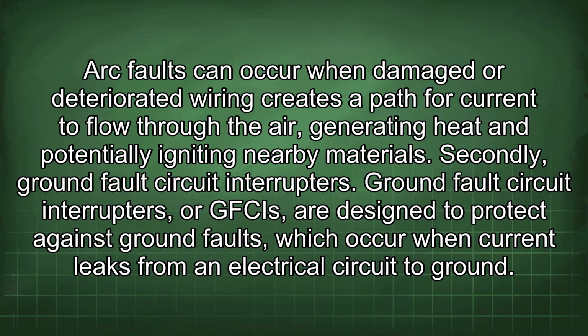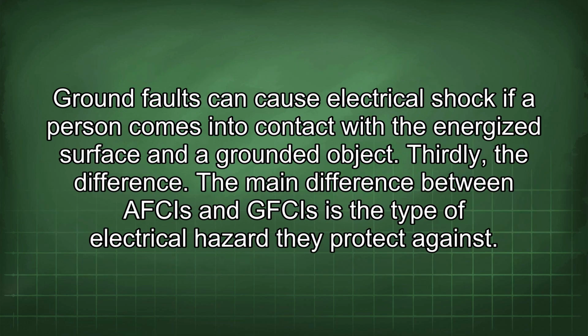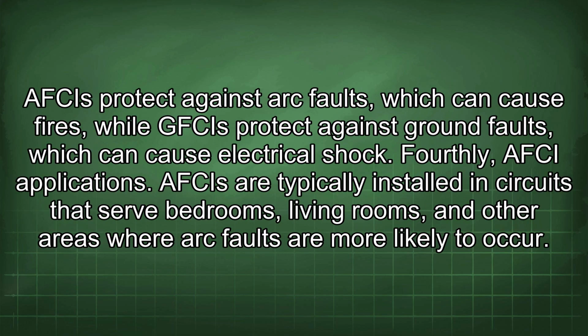Secondly, ground fault circuit interrupters. Ground fault circuit interrupters, or GFCIs, are designed to protect against ground faults, which occur when current leaks from an electrical circuit to ground. Ground faults can cause electrical shock if a person comes into contact with the energized surface and a grounded object. Thirdly, the difference. The main difference between AFCIs and GFCIs is the type of electrical hazard they protect against. AFCIs protect against arc faults, which can cause fires, while GFCIs protect against ground faults, which can cause electrical shock.